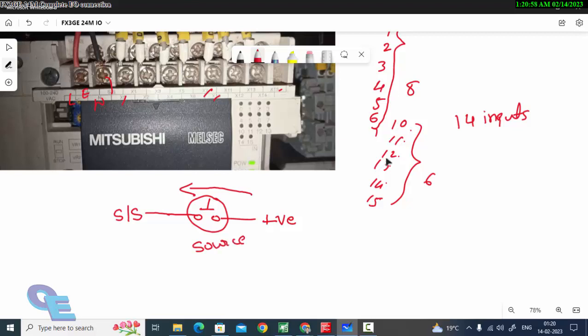So we have to consider this a source type of connection. Sink type of connection is when the S by S terminal is directly connected, and if we connect from negative to the negative terminal, then we can call this sink type connection - meaning current flows from PLC to field device instead of field device to PLC. This type is called source type connection.